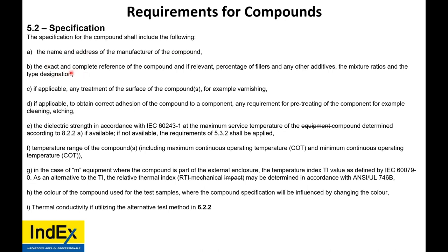So the specification for compounds says you have to have the name and the address of the compound, the exact and complete reference of the compound, percentage of fillers, any treatment required, how to obtain the correct adhesion, the dielectric strength, the temperature range, the external enclosure and temperature, the color of the compound used for testing, what color it changes to, and the thermal conductivity. There's a lot of things involved.